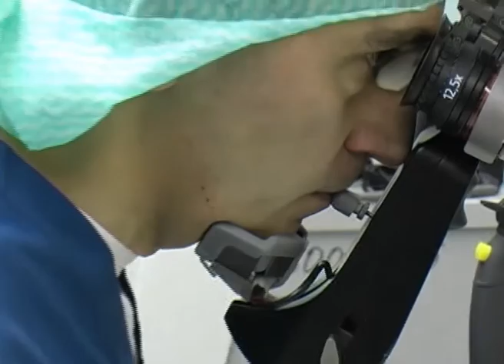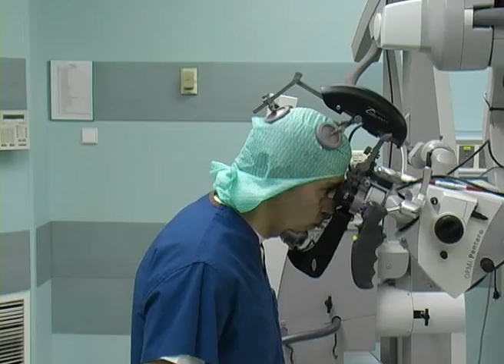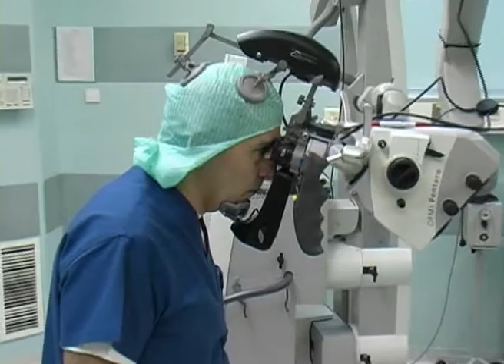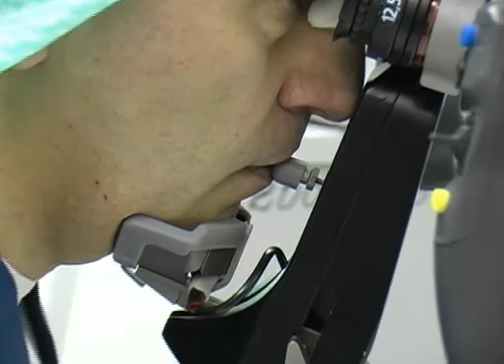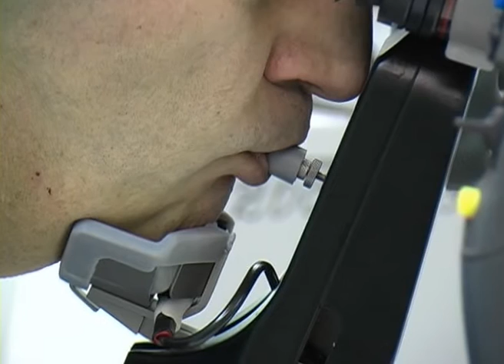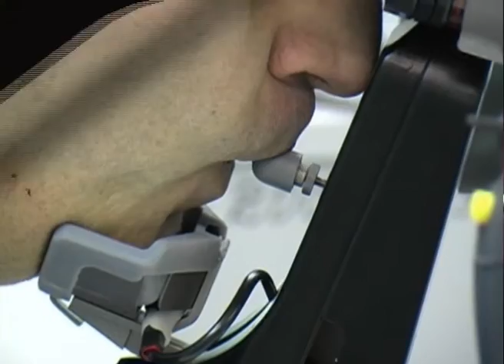By pressing the joystick, the surgeon can unlock the device and release his or her head. The device permits hands-free control over the microscope's optic system. The multifunctional joystick provides not only closing and opening of the device, but also adjustment of focus and zoom. Slight motions of the surgeon's lips to the right, to the left, upwards and downwards provide the transmission of the corresponding signal, focus up, focus down, zoom in and zoom out, to the microscope control system.